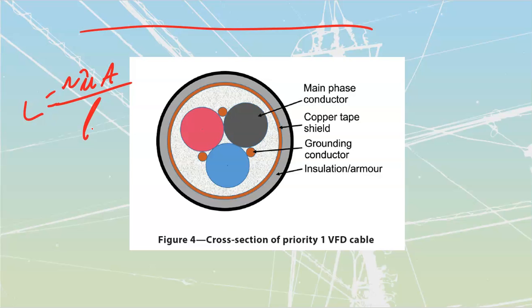Altogether, all the experimentation in the field, what people were figuring out, and what manufacturers were dealing with, led to the development of what we refer to as Priority 1 VFD cable. There are other priorities, Priority 2, 3, etc., but the most common one is Priority 1. It's made up of 3 main phase conductors.